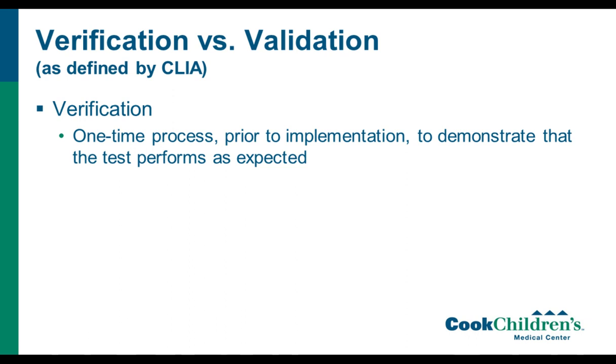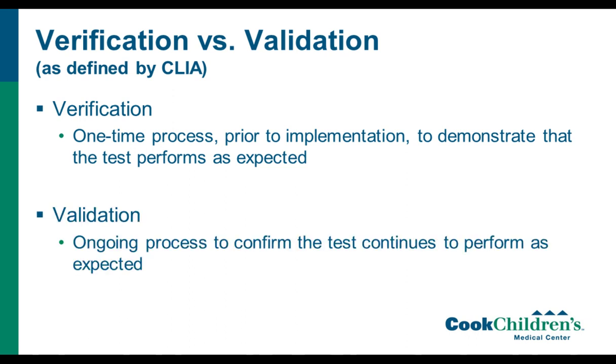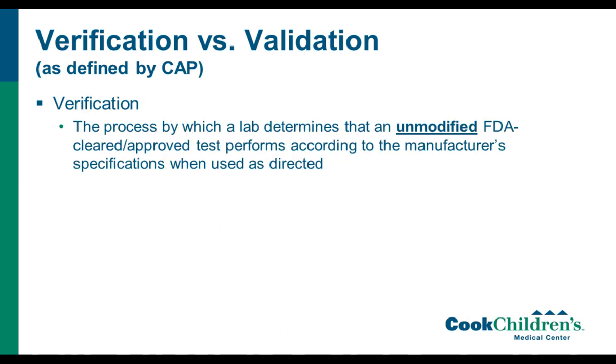And this is actually a little bit confusing because different groups have different definitions. So as defined by CLIA or the government, verification is a one-time process prior to implementation of the assay where you're demonstrating that that test performs as expected. And their definition of validation is an ongoing process to confirm that the test continues to perform as expected. So I would say most people do not use these definitions, but instead more refer to the CAP definitions.